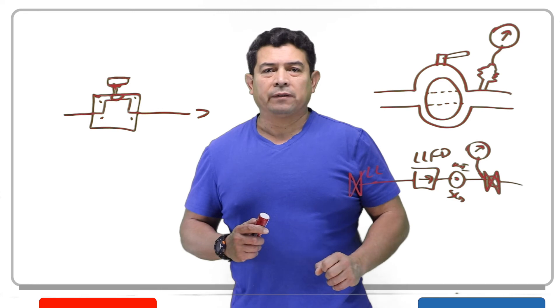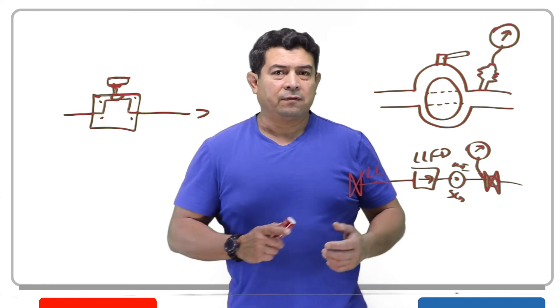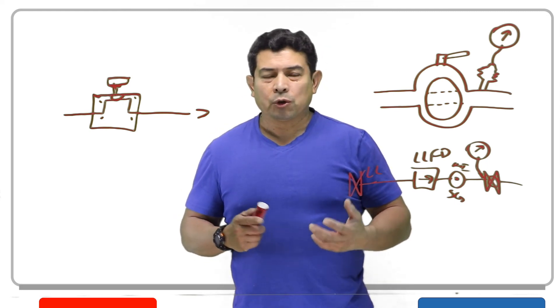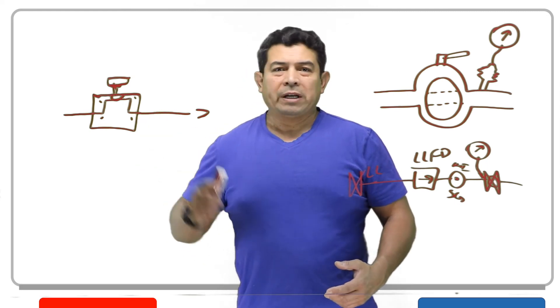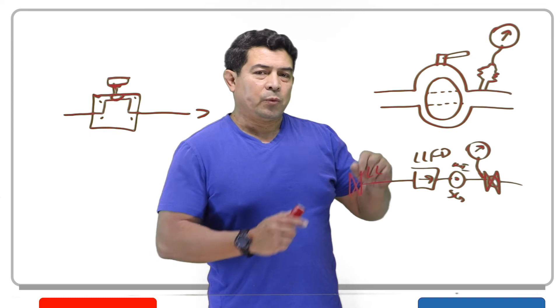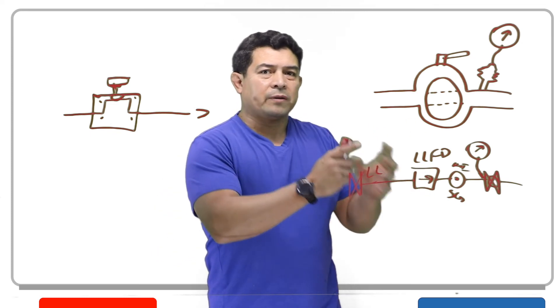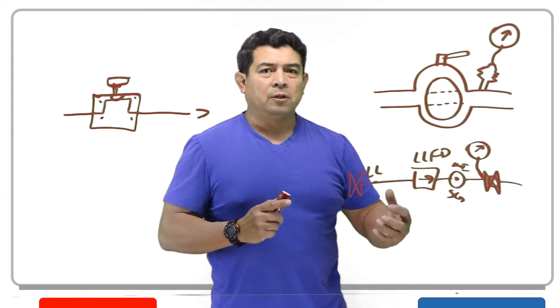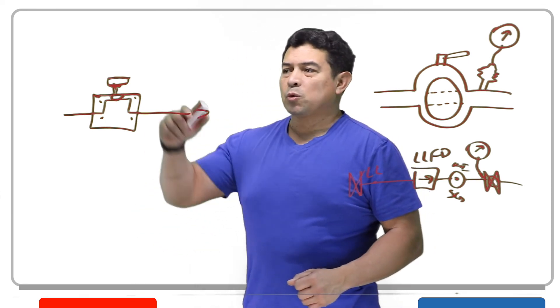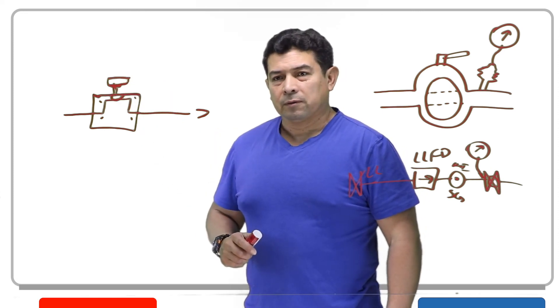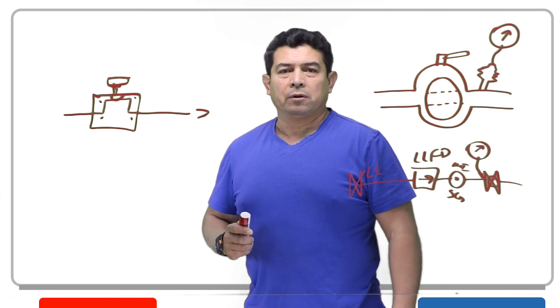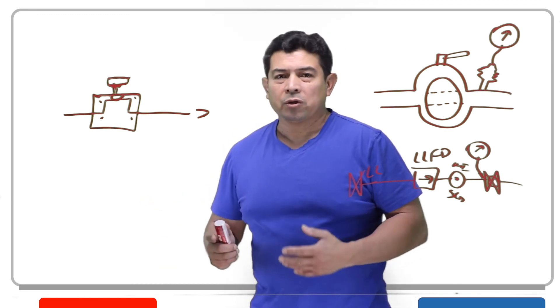So now instead of having a TXV, a thermostatic expansion valve, or a piston, or a capillary tube or anything like that, we would have these and someone would have to sit there and actually adjust and control the flow so that we could maintain the evaporator at a certain temperature and maintain the room at a certain temperature. That would be one of the purposes for this when you need to actually adjust the flow. Because you're adjusting the flow, all of these 90 degree turns are not going to hurt anything.